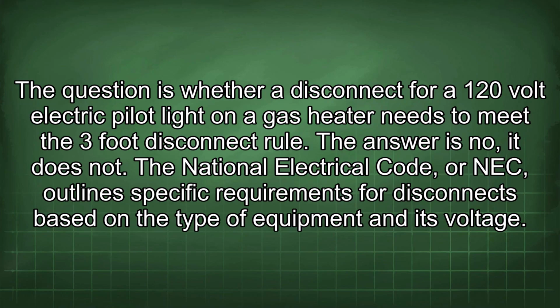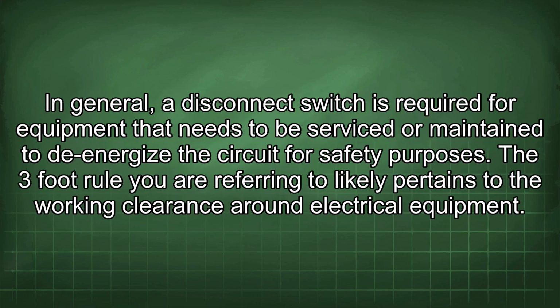The question is whether a disconnect for a 120-volt electric pilot light on a gas heater needs to meet the 3-foot disconnect rule. The answer is no, it does not. The National Electrical Code, or NEC, outlines specific requirements for disconnects based on the type of equipment and its voltage. In general, a disconnect switch is required for equipment that needs to be serviced or maintained, to de-energize the circuit for safety purposes. The 3-foot rule you are referring to likely pertains to the working clearance around electrical equipment.